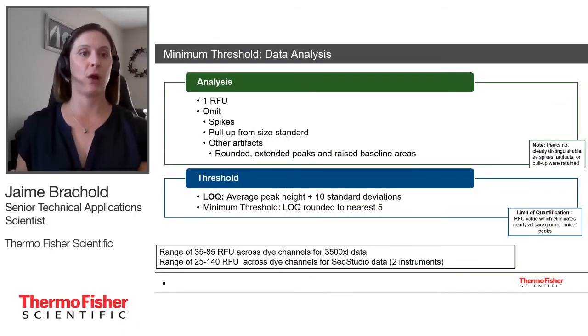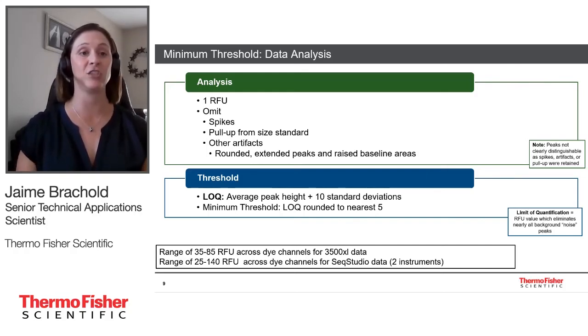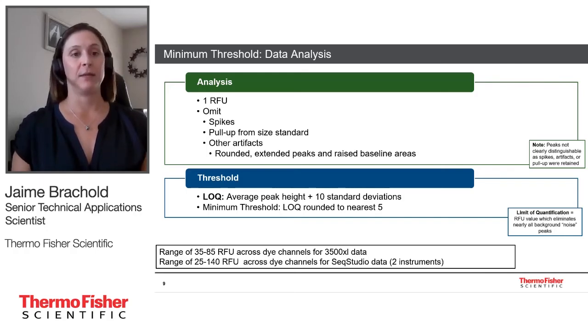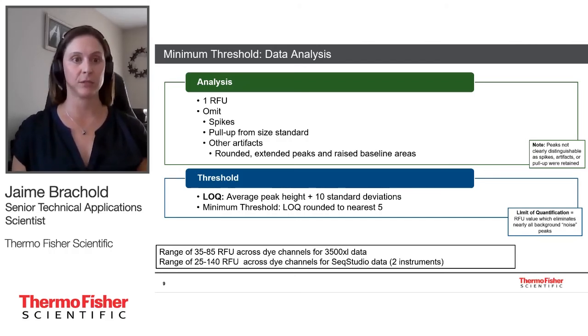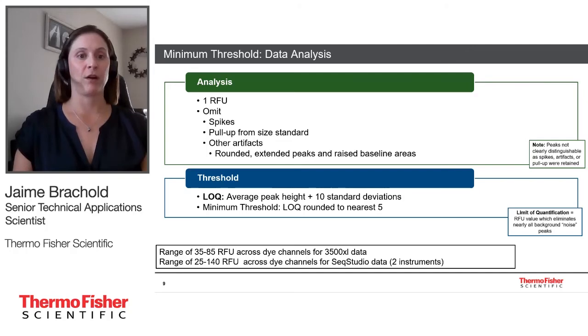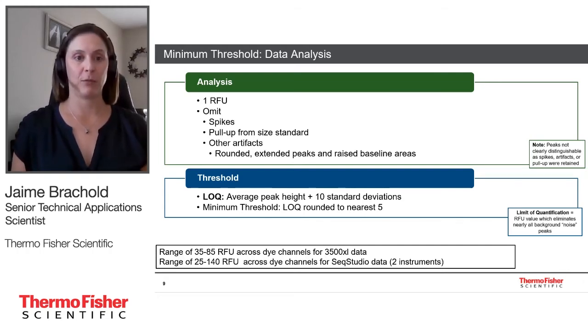We used minimum thresholds for analysis, calculated by analyzing non-template control data for each kit on each instrument at one RFU, editing out any pull-up, spikes, or artifacts from the size standard. We then calculated the limit of quantification — the average peak height of all non-artifactual peaks plus 10 standard deviations — and rounded to the nearest five to set the minimum threshold. On the 3500, thresholds ranged from 35 to 85 RFU across the dye channels across five chemistries. On the SeqStudio across two instruments and all chemistries, the range was 25 to 140 RFU.